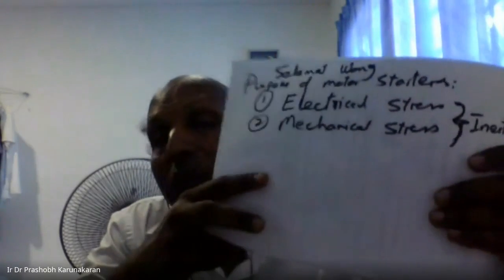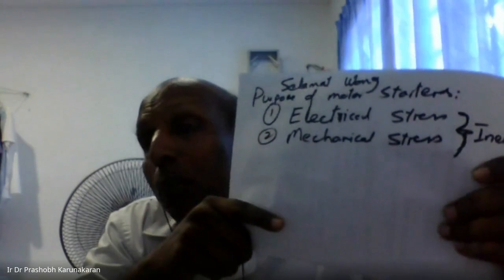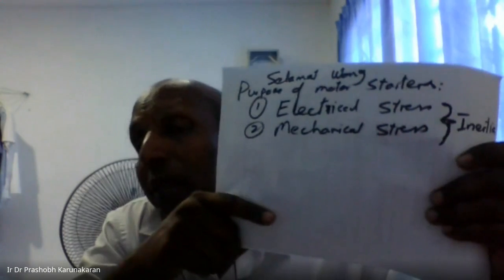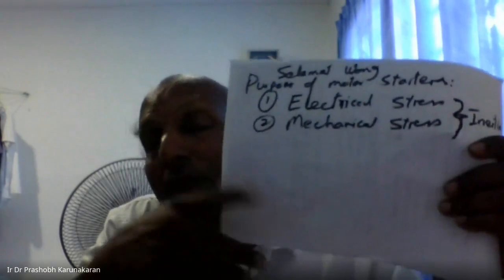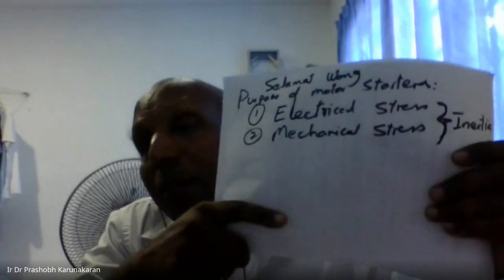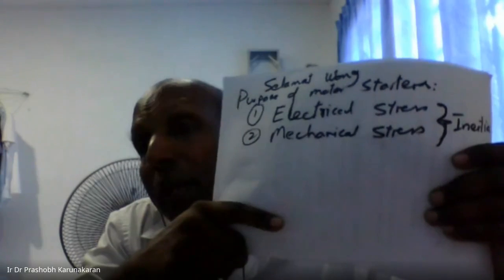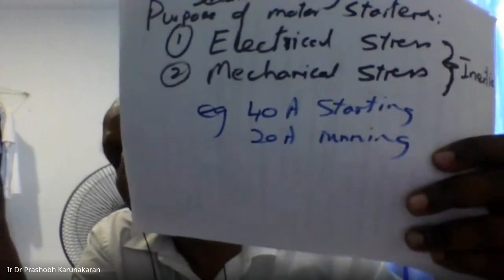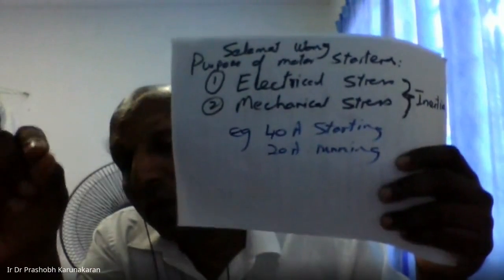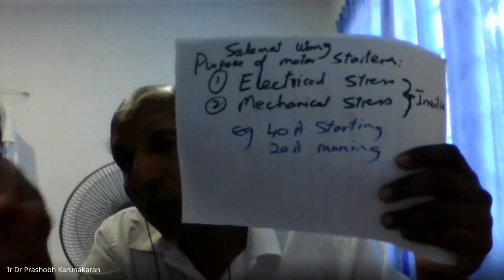Normally, in most cases, for a big motor as big as a classroom, the amp that it pulls in during starting to overcome the inertia is double. I asked one of the engineers, who was my student in Taiwan, to measure. So the starting is 40 amps, the running 20 amps. That's why the final device before going to the motor is called the overload relay.